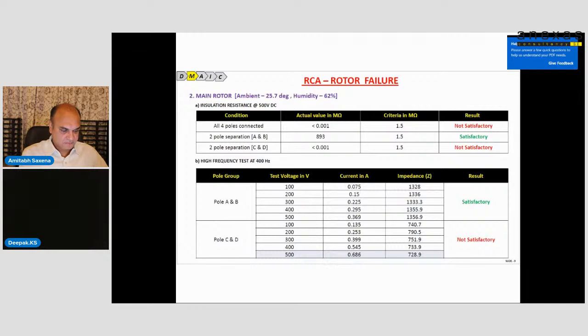Now we did the insulation resistance on the main rotor. This particular rotor is a 4-pole machine. All the 4 poles were connected and we checked the insulation resistance. It was not okay. It was not meeting the criteria. The criteria is 1.5 mega ohm. It was less than that.